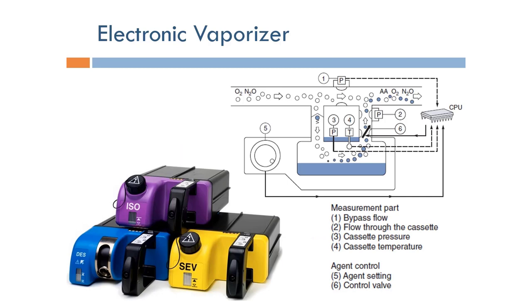Alternatively, electronic vaporizers do everything that the mechanical vaporizer does, but in electronic form. We still have a bypass path and a path through the inhalation anesthetic, but here the flow is controlled by an electronic valve. We measure temperature, pressure, and other parameters so that we can accurately control the mixing and achieve exactly the desired concentration output. This electronic form requires electrical power, but provides much more accurate compensation for temperature and pressure variations inside the vaporizer, making it somewhat more accurate than the mechanical vaporizer.